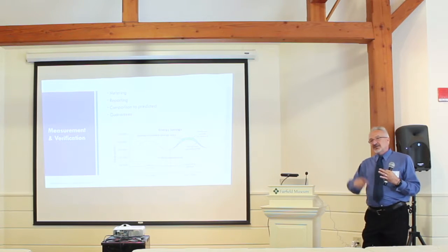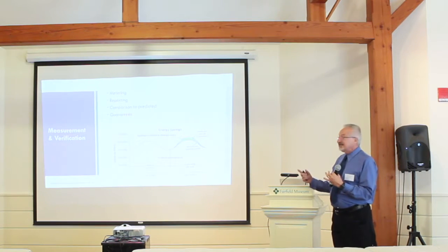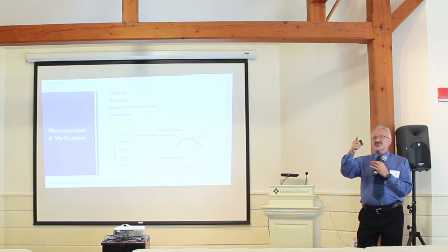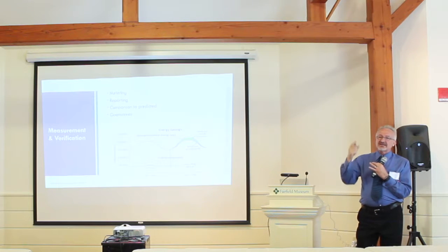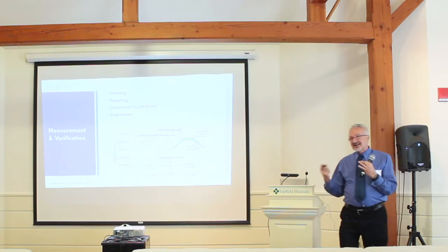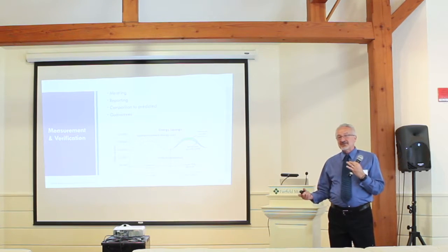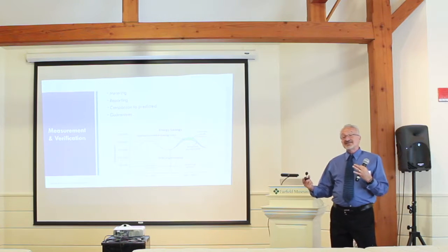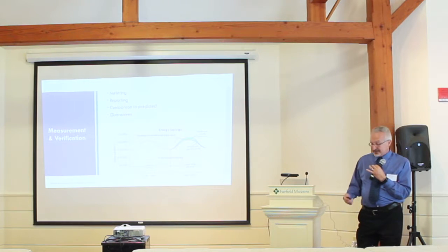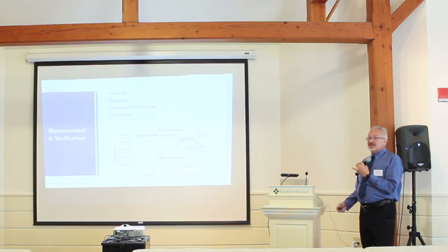Or, gee, we closed that wing of the building, we're not using that wing of the building. Or when we originally did the model for the baseline, oh, well, we didn't tell you that the air conditioning that you upgraded hasn't worked in over a year. So your baseline really isn't accurate, because the air conditioning they replaced never even ran before. It was inefficient, but it didn't run. So we took credit for energy that wasn't being utilized. These are all things to be taken into consideration with measurement and verification.